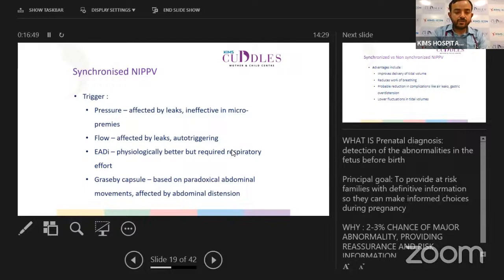The most commonly used trigger mechanism in India, at least, is the pressure sensing, in which the ventilator detects a change in the pressure noted within the ventilator tubings during baby's inspiratory efforts and thereby triggers the inspiratory breath. But the problem with pressure triggering is it's affected by leaks and it is ineffective in micropremies as they don't have sufficient muscle strength to generate changes in pressure in the ventilator circuit.